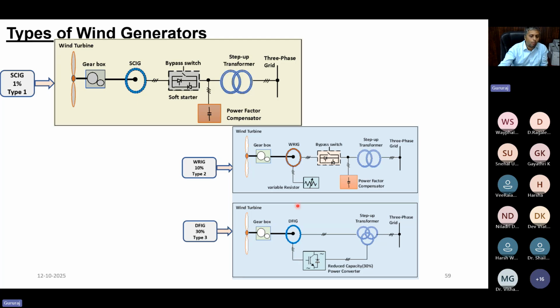So type 3 is a very popular one. Why I call it popular is because the speed variation is very much connected to practical reality. Most of the wind turbines that we see being installed across the country require speed variations of around plus or minus 30%. The wind speed varies within that range, eventually leading to power variations of plus or minus 30%. Hence, you can use partially rated converters at the rotor side, which can help you extract maximum power, control the reactive power flow, or help you sustain fault ride-through behavior.